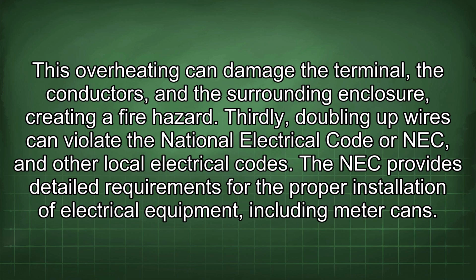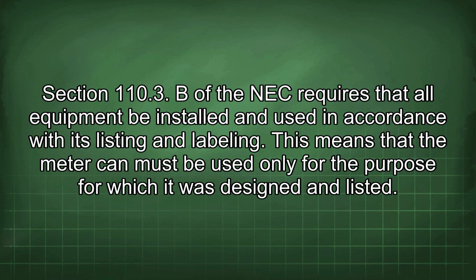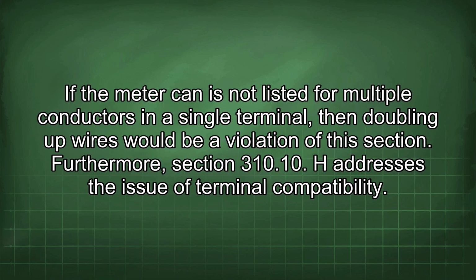Thirdly, doubling up wires can violate the National Electrical Code, or NEC, and other local electrical codes. The NEC provides detailed requirements for the proper installation of electrical equipment, including meter cans. Section 110.3(B) of the NEC requires that all equipment be installed and used in accordance with its listing and labeling. This means that the meter can must be used only for the purpose for which it was designed and listed. If the meter can is not listed for multiple conductors in a single terminal, then doubling up wires would be a violation of this section.